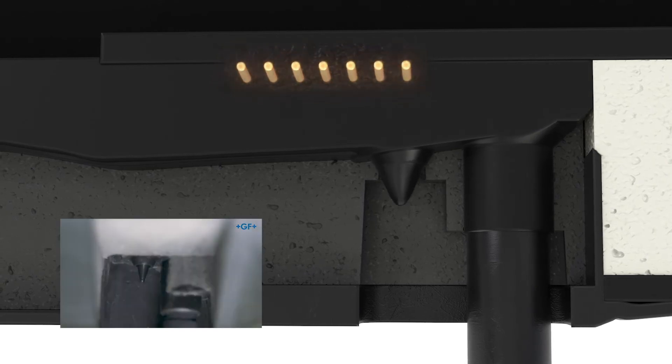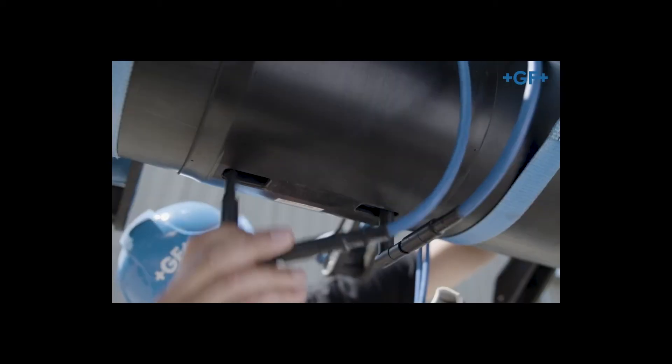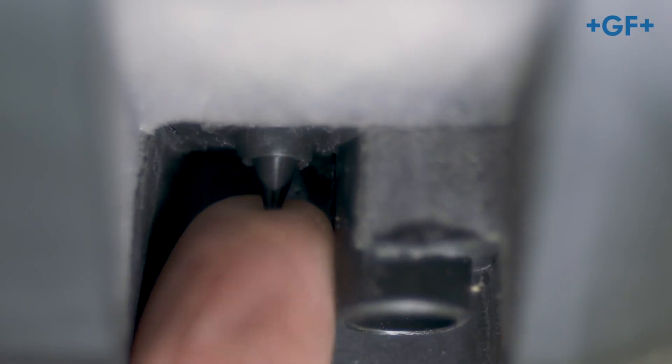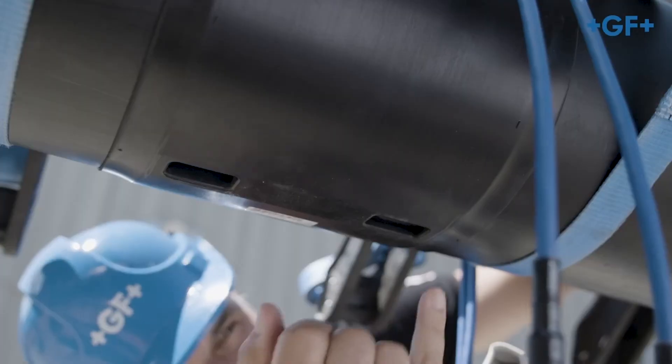After welding, check the notification of the welding unit and remove the cables connected to the fitting. Check both fusion indicators of the fitting as shown here.